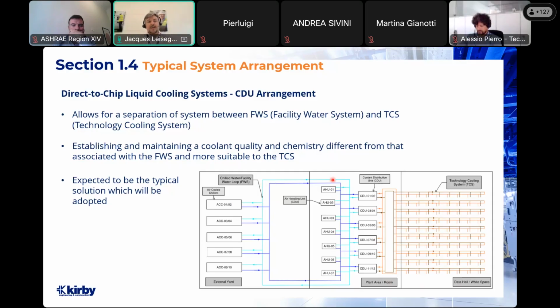So the water chemistry in the technology cooling system is very specific, and it's at a very high standard. A high level of filtration is needed on that system. So if we separate the two systems, we can manage the water chemistry of the technology cooling loop that much better, that much closer. And again, as we mentioned, we can reduce the system volume.